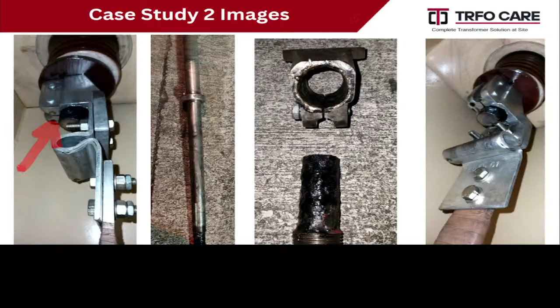This is OLTC failure. This is a 105 MVA, 400 kV class transformer. The complaint was that an OLTC fault occurred at that particular site. So the customer called for the inspection. We drained the oil and checked the internal core coil assembly. Nothing had happened to the core coil assembly. We tested the transformer at site. Everything was fine and superb.